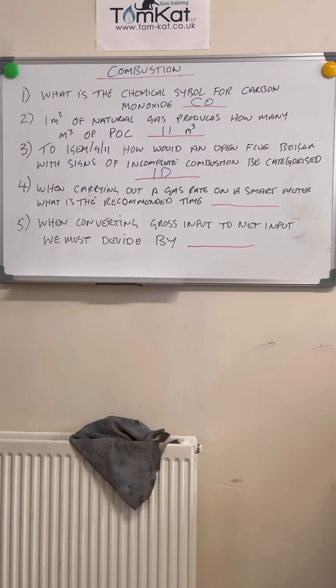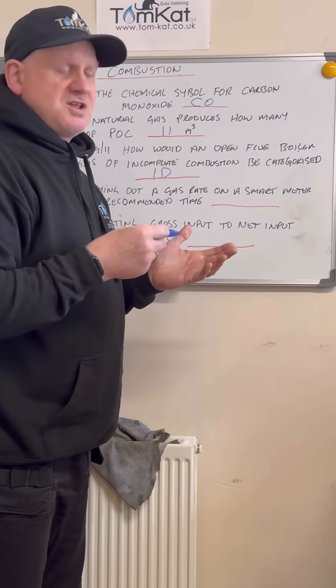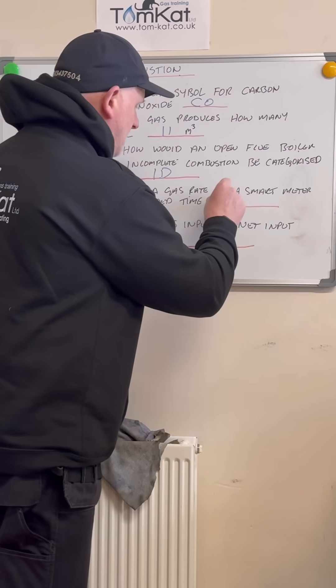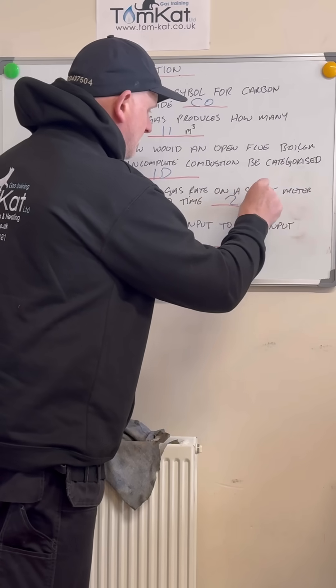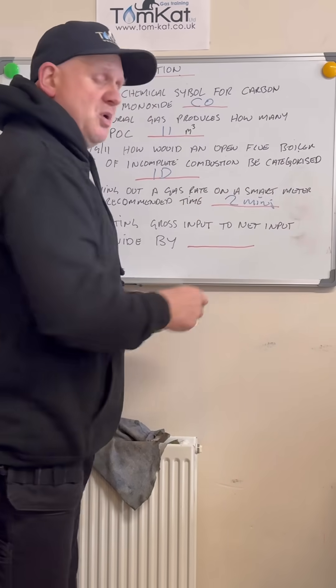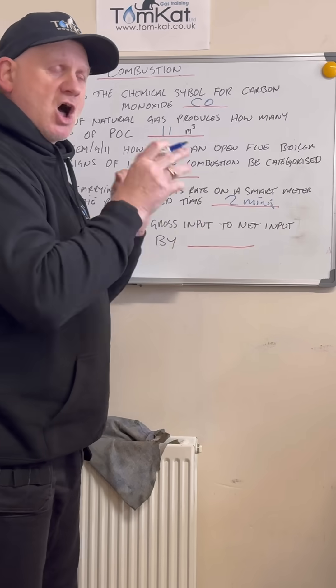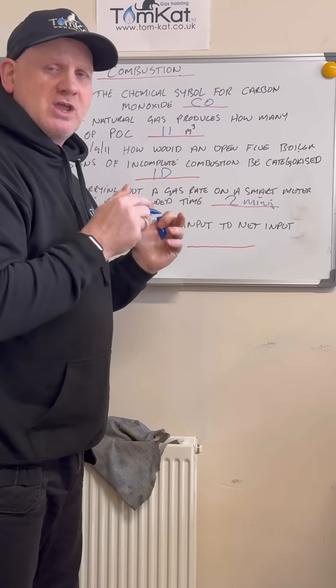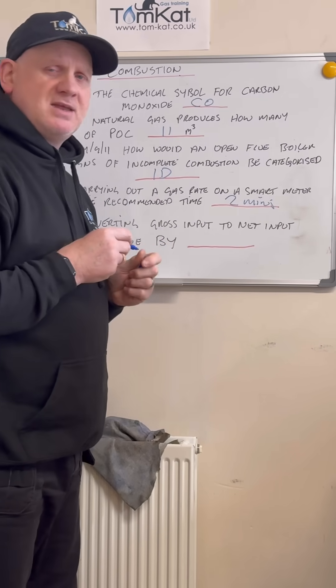Question number four. When carrying out a gas rate on a smart meter, what is the recommended test time? On a smart meter the minimum time we can do it is two minutes. But if the numbers are always shown on the gas meter, then we could reduce that to one minute.